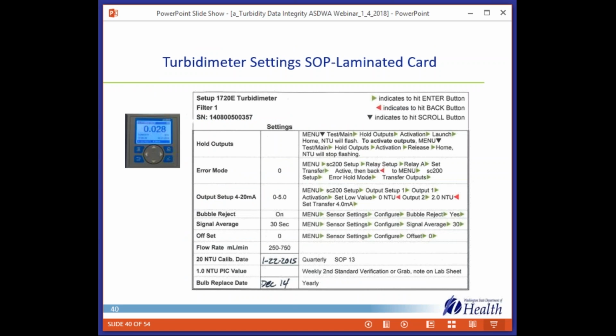Here's an example of an excellent SOP. It's a laminated card. This is from Tacoma's water treatment plant. They have this laminated card at each device. It's awesome. So it's clear what the instrument is. Here's the serial number for the instrument. And then they have different settings, the values, and then the best part I like is here's how you get through the menu. Here they have the date of their last primary calibration and the date of when they last replaced the bulb. It's right there at the device.